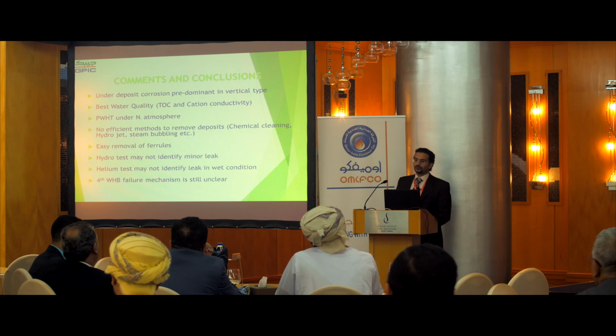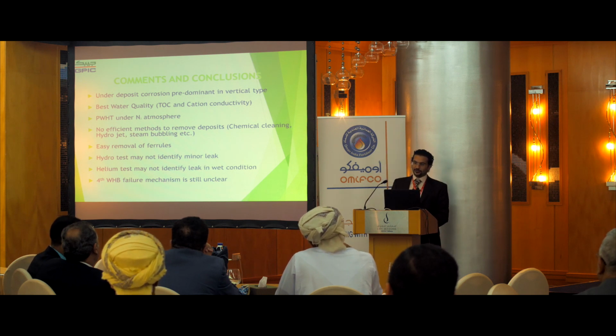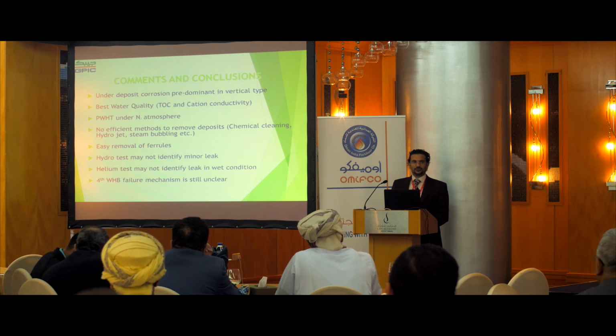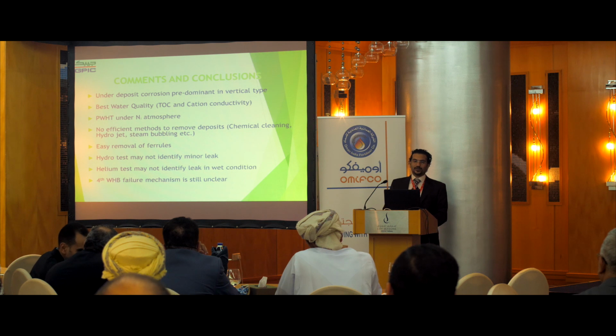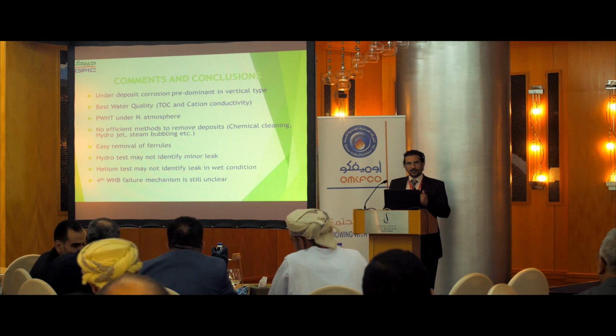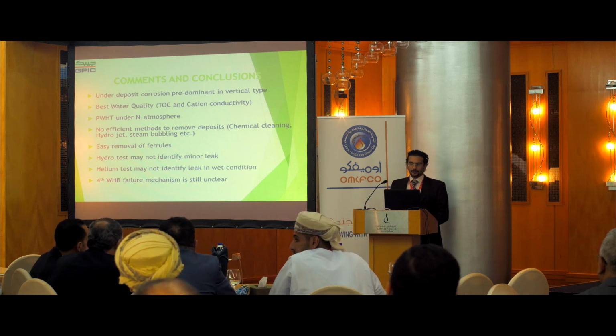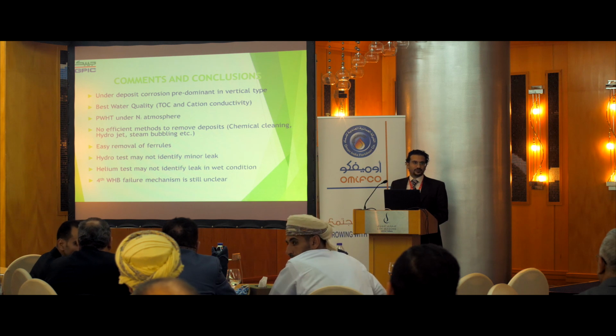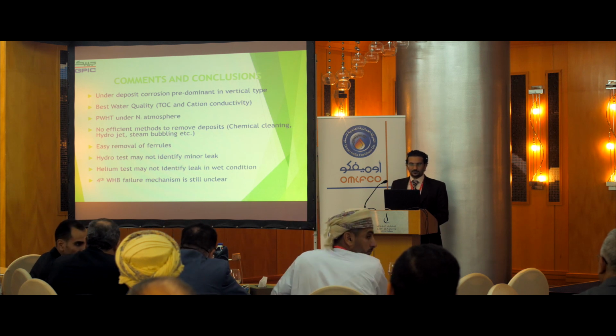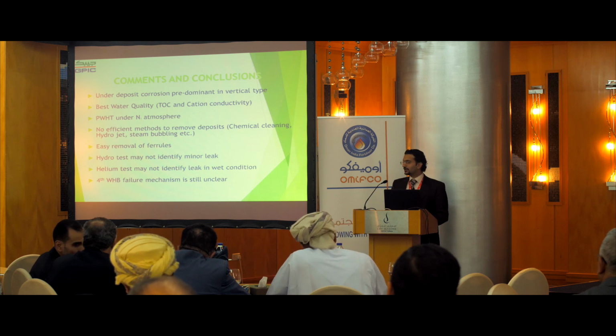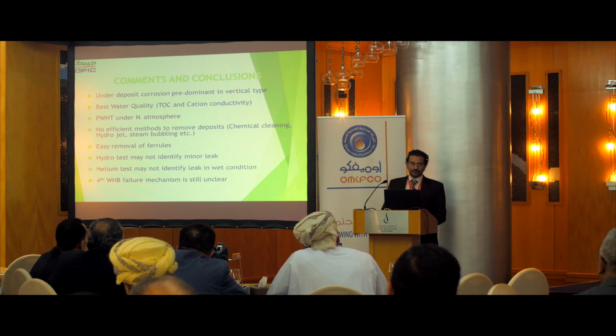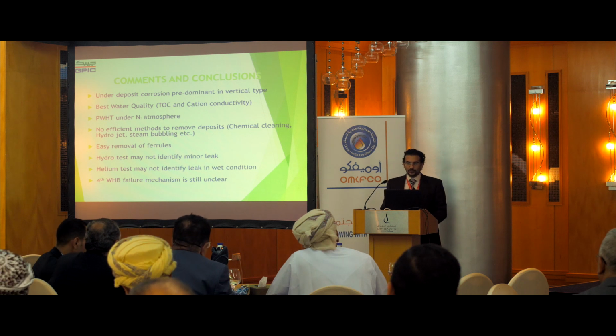So, comments and conclusion: under-deposit corrosion is predominant in the vertical type. The best water quality control is to keep close monitoring of the TOC and the cation conductivity. The post-weld heat treatment, the new method, is under nitrogen atmosphere, which is different from the others, which were under oxidized condition. There is no efficient method to remove deposit, but maybe this new dry ice method could help. Easy removal of the ferrules.